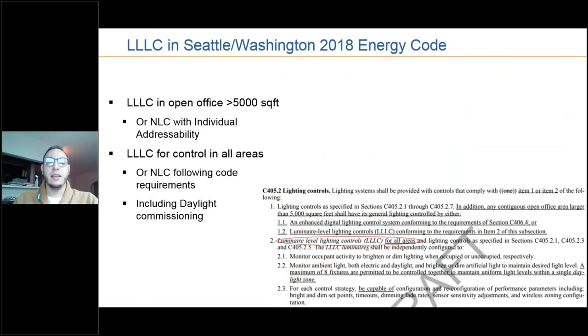So when we say that LLLC automatically meets code, what exactly do we mean? Well, now with the 2018 Seattle and Washington Energy Code, there is a requirement for open offices 5000 square feet or greater to have luminaire level lighting control written in the code. Or if you cannot have LLLC to meet that code, you will need to have a network lighting control system with individual addressability, so almost an LLLC application.